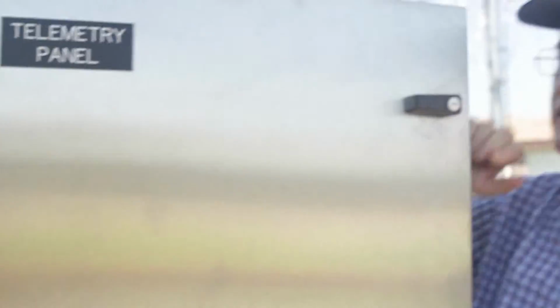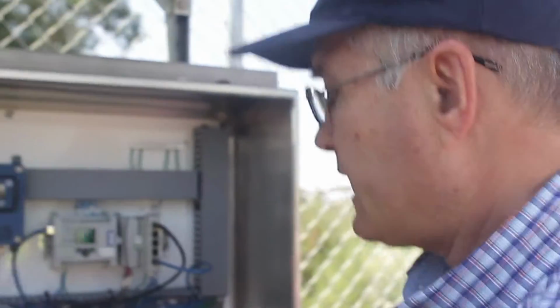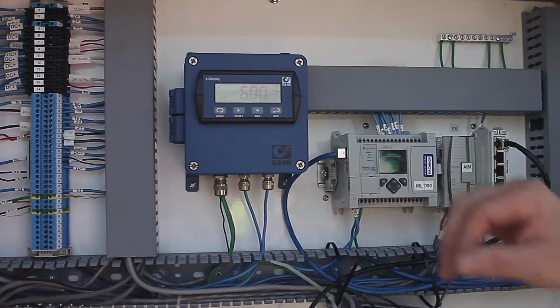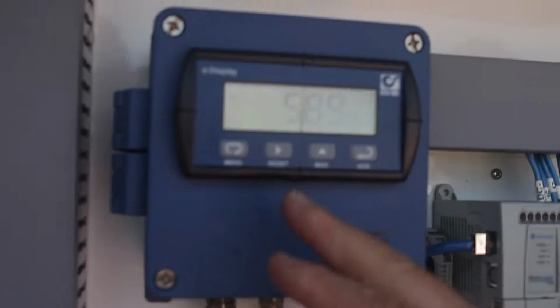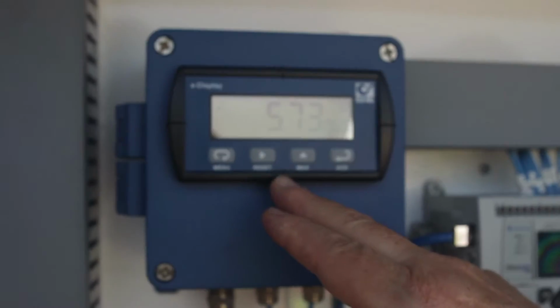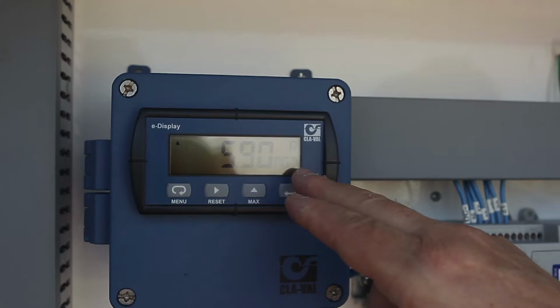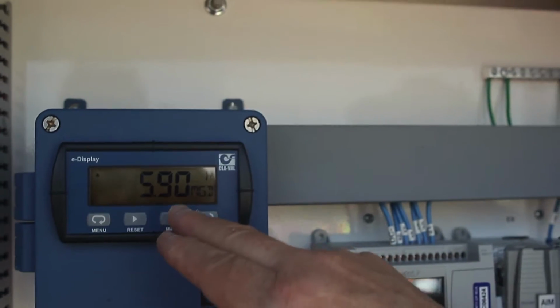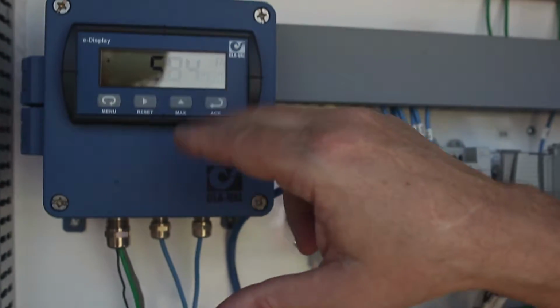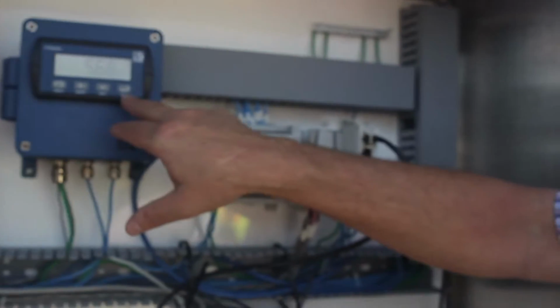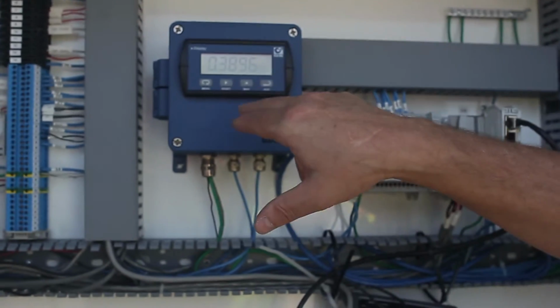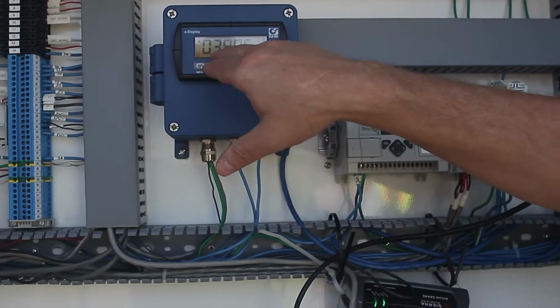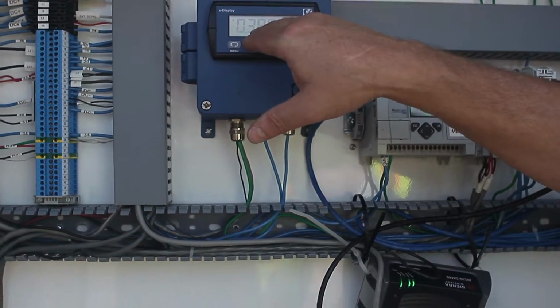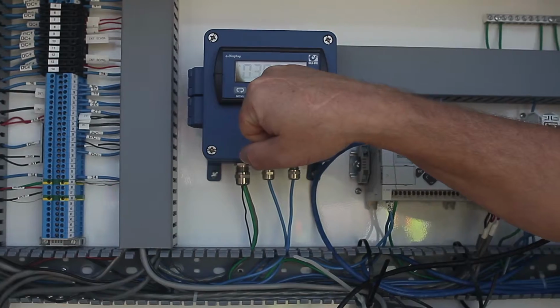This is the equipment being powered by the generator and the batteries. And as we can see, there's not a lot here. It's pretty low power instrumentation. The flow meter from the valve is coming into a digital panel meter, reading out in million gallons per day. Right now we're just below 6 mgd flow rate. This panel meter shows not only rate but also a local display of total. So right now, since I zeroed it out less than an hour ago, we're up around 0.4 million gallons.